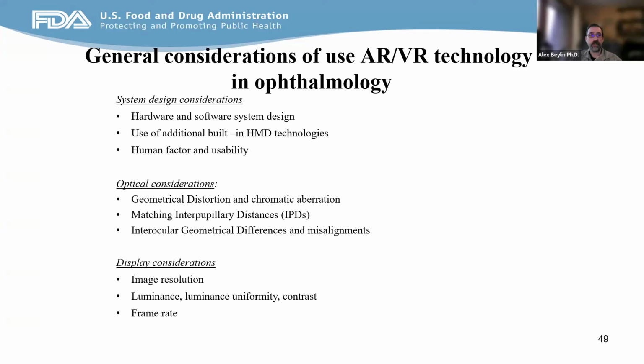Display considerations, which may include image resolution, luminance uniformity, and contrast of the display, are important for image quality of virtual content. Frame rate, depending on the application, may be part of the therapeutic or algorithm, so it's important that the selected device supports the necessary frame rate. Please note that due to multiple specific requirements, the majority of head-mounted displays used in ophthalmology are device-specific. Therefore, the device should be validated with the specific compatible model of HMD.